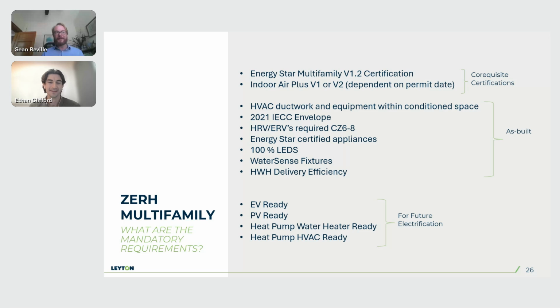Thanks, Ethan. I just wanted to jump in and talk about the requirement for having the ductwork within conditioned space, just because I know for a lot of builders that's actually a reason to not pursue zero energy ready homes. There are some exemptions, particularly if you're using spray foam insulation, where you can put them into places that are not conditioned. Similarly, there's a company I've seen recently, I believe based in Arizona, that has created a ductwork system specifically to meet zero requirements to make sure all their ducts stay in conditioned space. So it sounds strict, but there are a lot of ways to be compliant with that requirement that you may not be aware of.